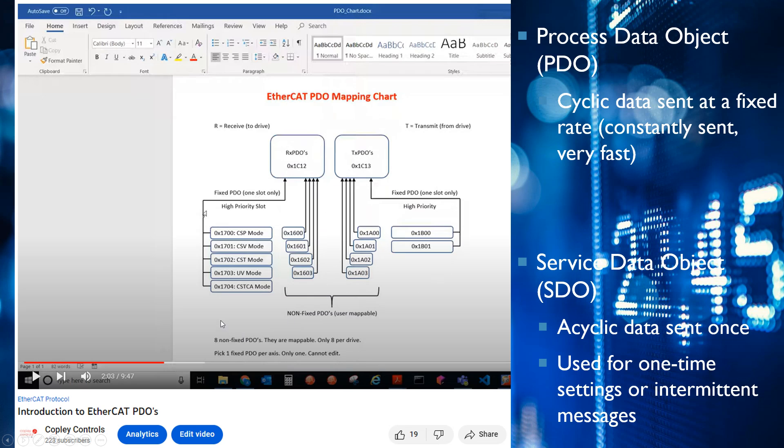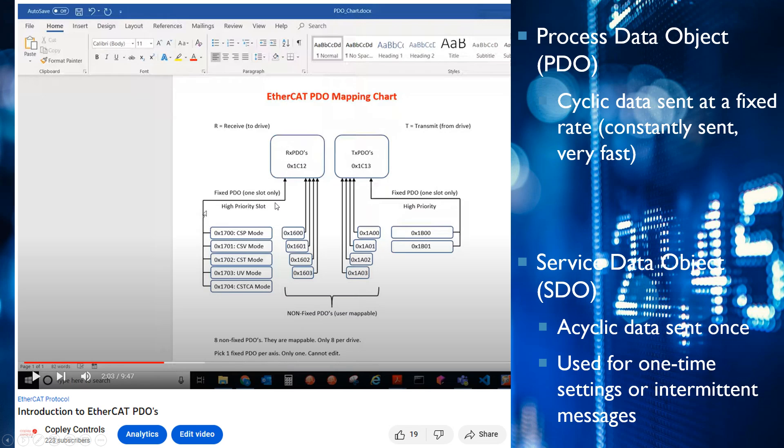Per node there are eight user mappable PDOs. You have four receive and four transmit, and then you have these fixed PDOs. You can only pick one fixed PDO per axis, and then you can use all eight of these if you wanted to.